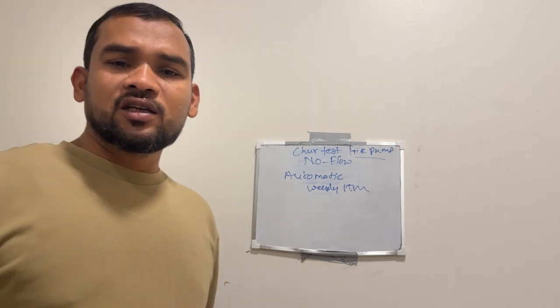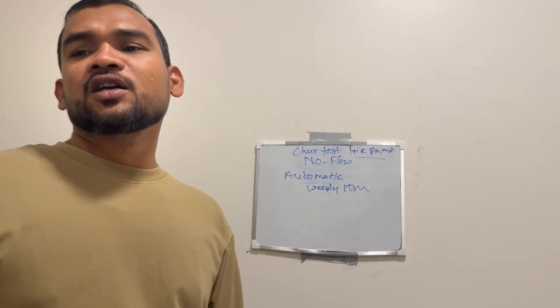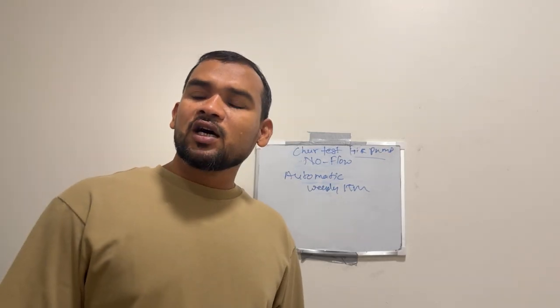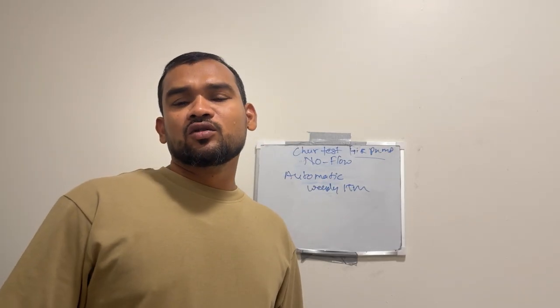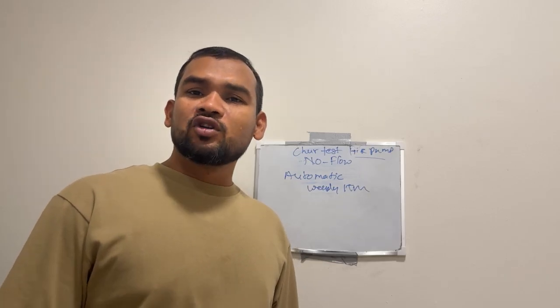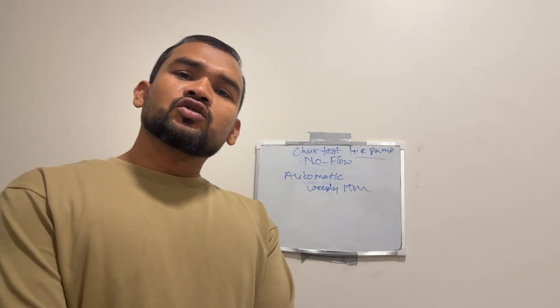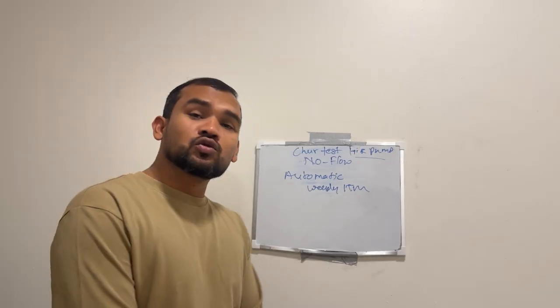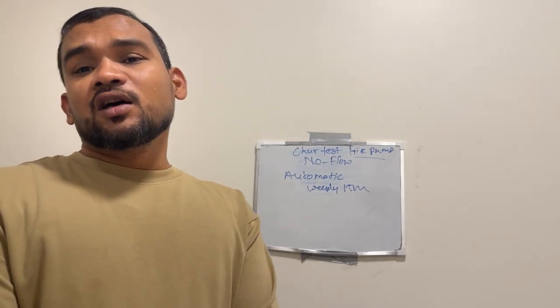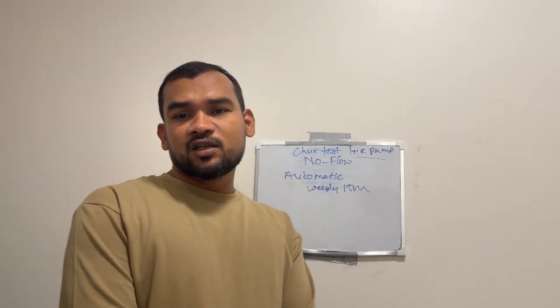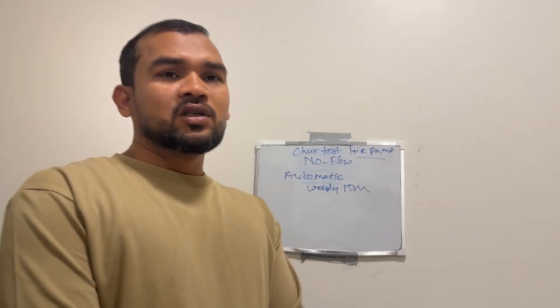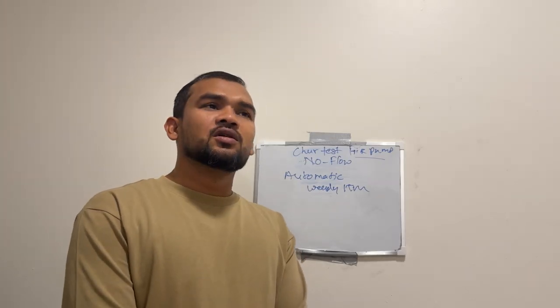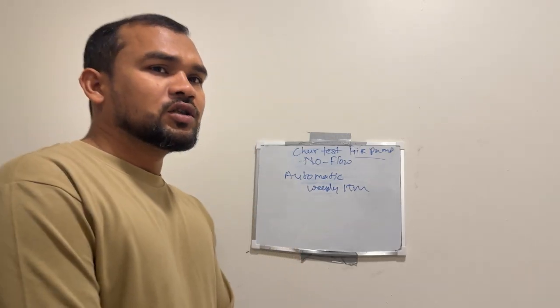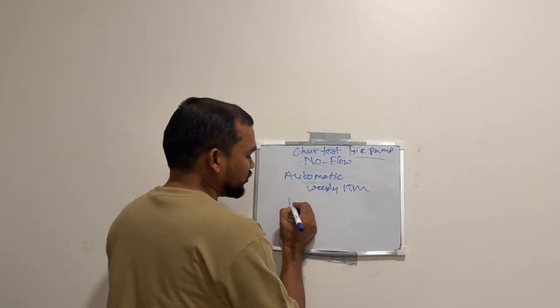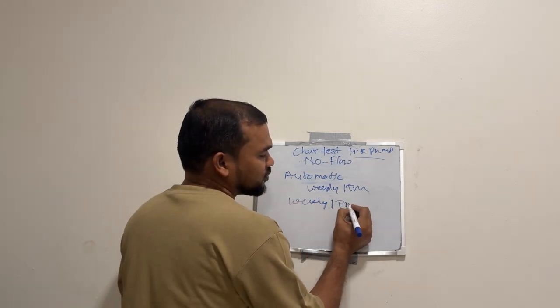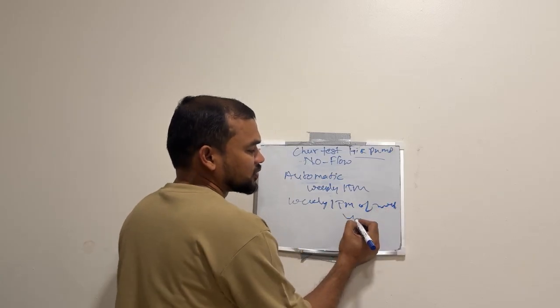As per NFPA 25 chapter 13, there is no testing required for the valves on a weekly basis, so there is no maintenance either. If there is any abnormality, finding, or observation, we have to correct it as soon as possible, inform the building owner, and correct it as per the manufacturer's instruction as soon as possible. The topic number 4: we have to check the fire protection water valves, the weekly ITM of which valves.